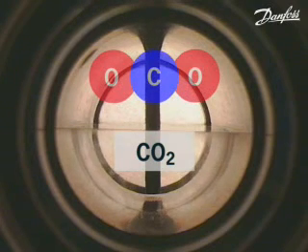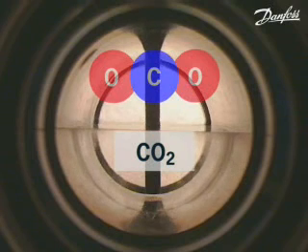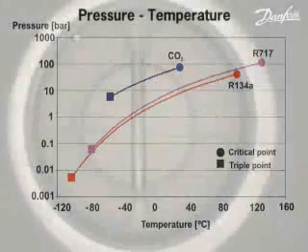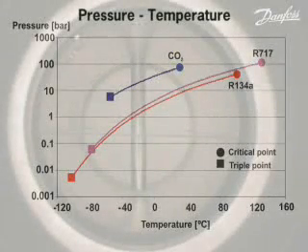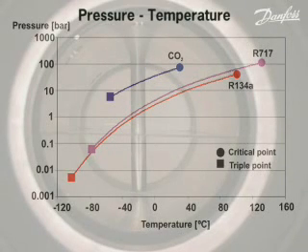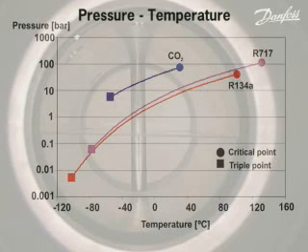The video shows the different phases of CO2 and how two of the phase changes occur by altering either the pressure or the temperature. When compared with commonly used refrigerants R134A and R717, CO2 has some unique characteristics. It operates at a much higher pressure but across a narrower temperature range than both R134A and R717.